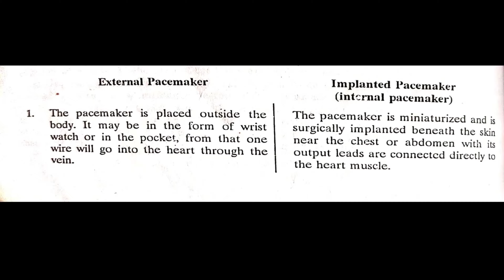Based on the placement of the pacemaker, there are two types of pacemaker: external pacemaker and internal pacemaker. In external pacemaker, the pacemaker is placed outside the body, and in internal pacemaker, it is surgically implanted. In external pacemaker, the electrodes are called endocardiac electrodes and are applied to the heart by means of an electrode catheter. In internal pacemaker, the electrodes are called myocardiac electrodes and are in contact with the outer wall of the myocardium, that is the heart muscle.